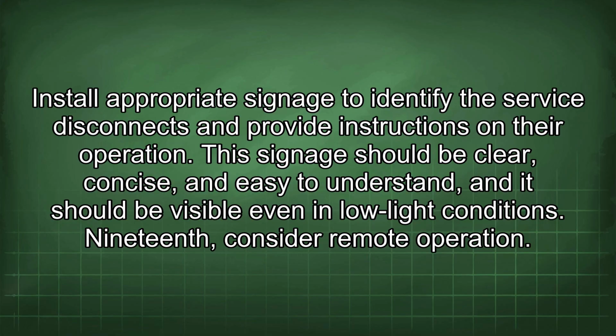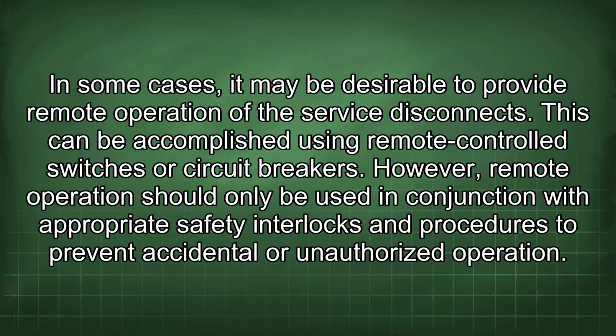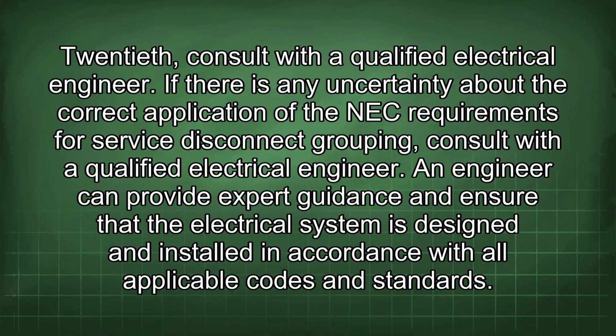19th, consider remote operation. In some cases, it may be desirable to provide remote operation of the service disconnects. This can be accomplished using remote-controlled switches or circuit breakers. However, remote operation should only be used in conjunction with appropriate safety interlocks and procedures to prevent accidental or unauthorized operation. 20th, consult with a qualified electrical engineer. If there is any uncertainty about the correct application of the NEC requirements for service disconnect grouping, consult with a qualified electrical engineer. An engineer can provide expert guidance and ensure that the electrical system is designed and installed in accordance with all applicable codes and standards.